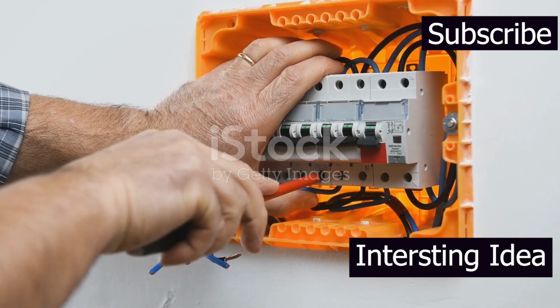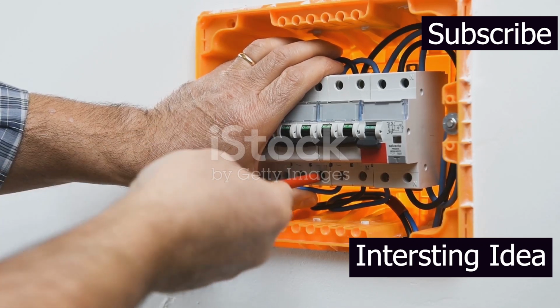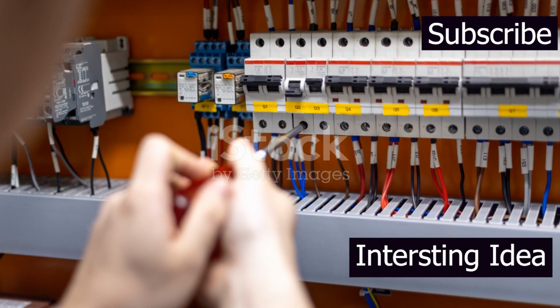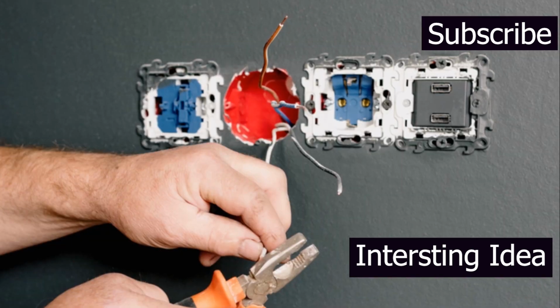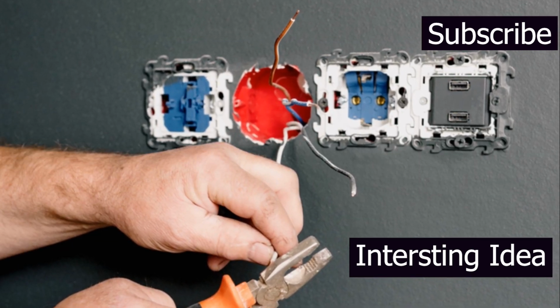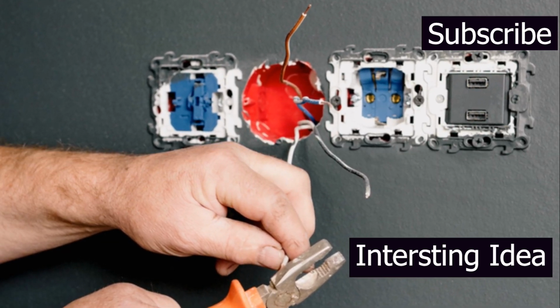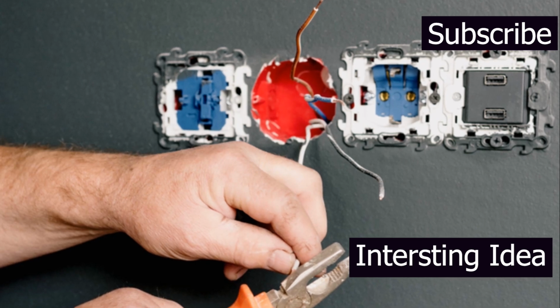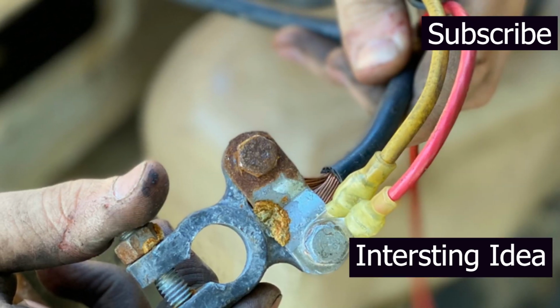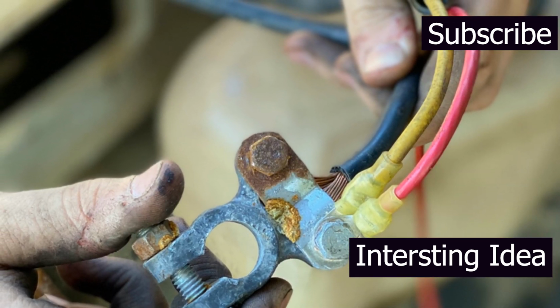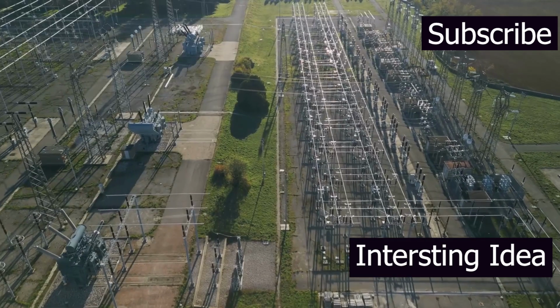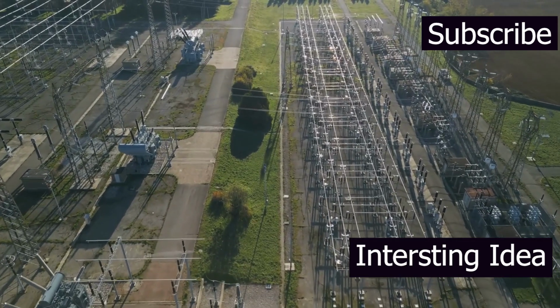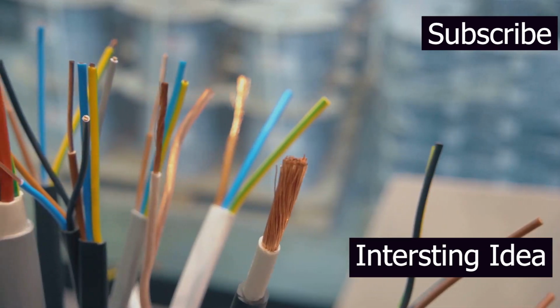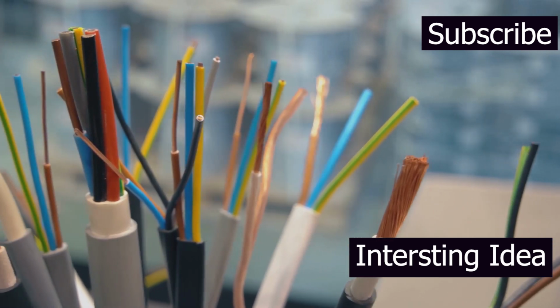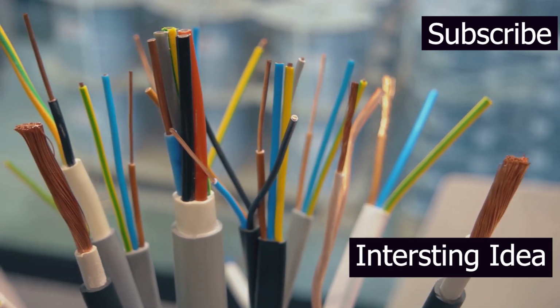Section 7. Connecting the dots. Wiring your electrical panel. With the circuit breakers installed, it's time to wire the panel. This step involves connecting the main power lines, grounding each circuit, and ensuring all connections are secure and properly insulated. Start by connecting the main power lines to the main breaker or lugs in the panel. These lines bring electricity from the utility company to your home. Use the correct wire size and type as specified by local codes and the panel manufacturer.